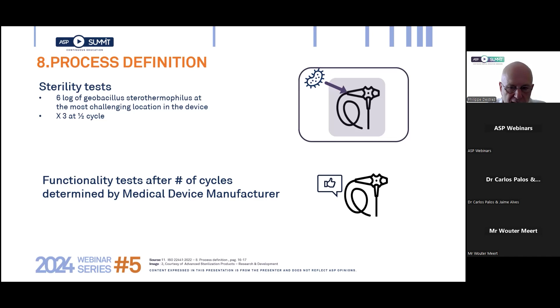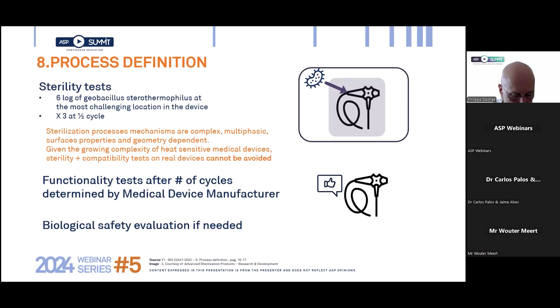What also needs to be done by medical device manufacturers is compatibility testing, that is repeating cycles on the device to make sure that after exposure to a large number of cycles, the medical device remains fully functional and fully safe for the patients. So again, I insist on the importance of medical device validation. I think that Wouter in his presentation will come back on that. With the growing complexity of medical devices, it's very difficult to simulate sterilization and functionality, and tests on real devices must be performed. It's important to keep in mind that this is under the responsibility of the medical device manufacturer. Can we go now to the next slide?